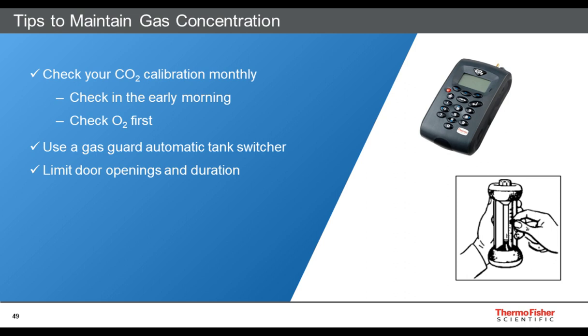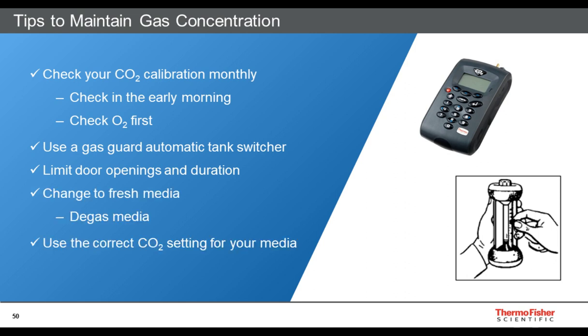Use a gas guard, an automatic tank switcher, so that if the CO2 tank runs out at night or on the weekend, you don't run out of carbon dioxide. And again, just like temperature, think about limiting the door openings and the amount of time that the incubator door is opened. If you're using hypoxia particularly, you might want to consider degassing the media, using nitrogen to bubble through the growth media before applying it to the cells.